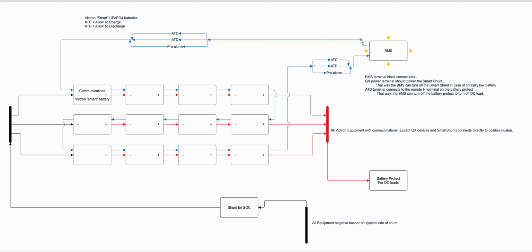The wires, there are three wires in this communication loop. They're titled ATC, ATD, and pre-alarm. That stands for allowed to charge, allowed to discharge, and pre-alarm. This is a simple continuity-based communications loop. So under normal operation, when everything's good, each battery allows continuity through on these three wires.